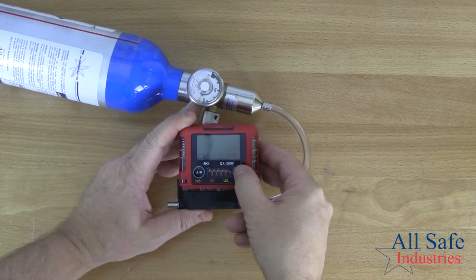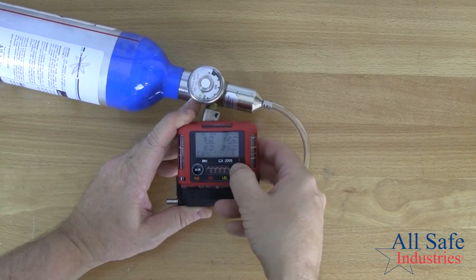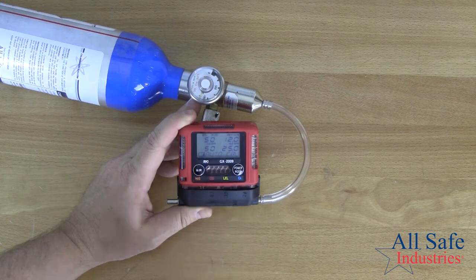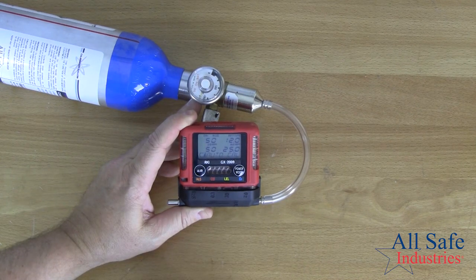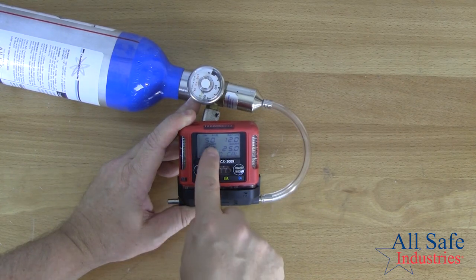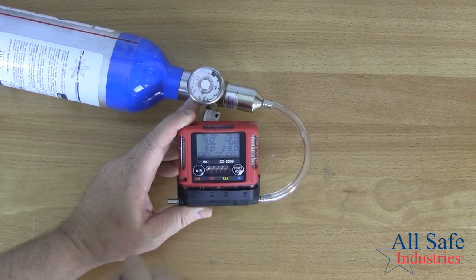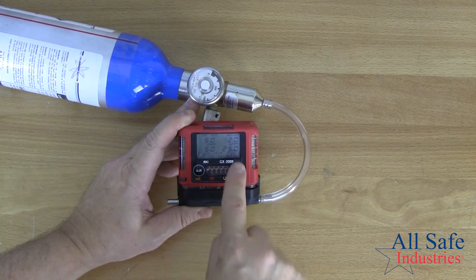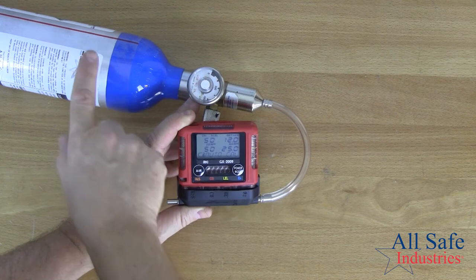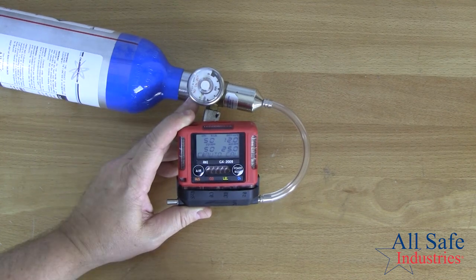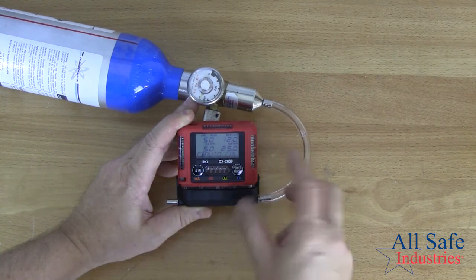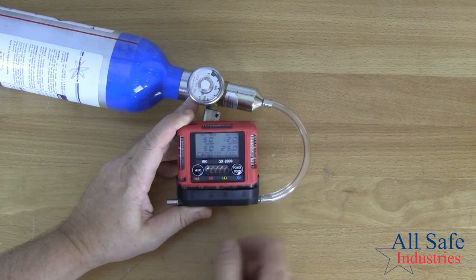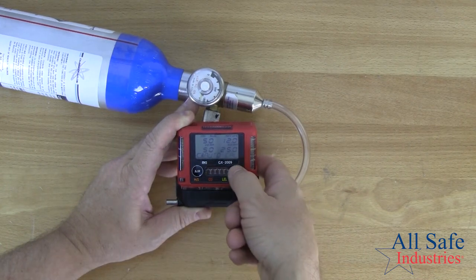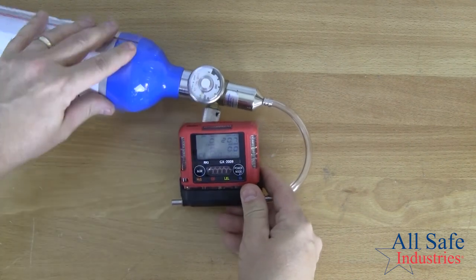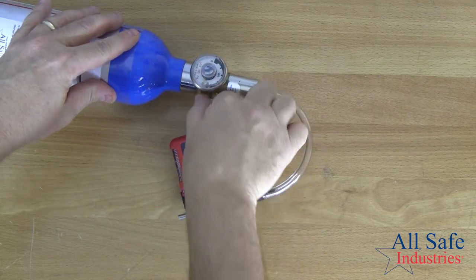So I'm going to select that menu by pressing power mode. And it's reminding me what my gas values should be when I'm calibrating. So there you see 50 for LEL, 12 for oxygen, 50 for CO, and 25 for H2S, the same values that I saw on the side of my cylinder just a second ago. So I want to do the automatic calibration, so I'm going to push power mode. And now the instrument's waiting for gas, so I'm going to turn the gas on.